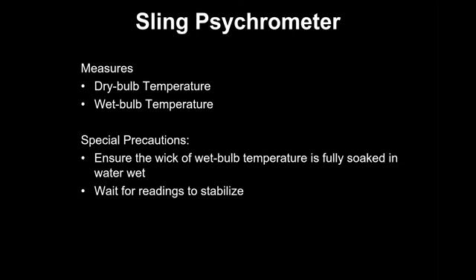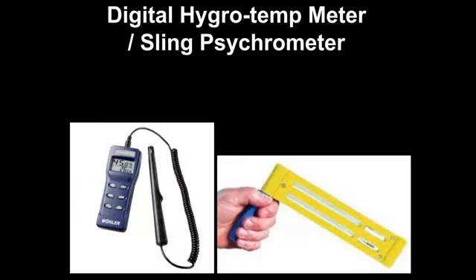We are still using it for cooling towers many times. At the top of the cooling tower, when we are doing the exhaust air analysis, we use a sling psychrometer, for the same reason as I said: any hygrotemp meter will get locked if the probe gets wet. These are two instruments. Normally this is 100% non-condensing, maximum what we have seen. So any condensation means it will just get locked.